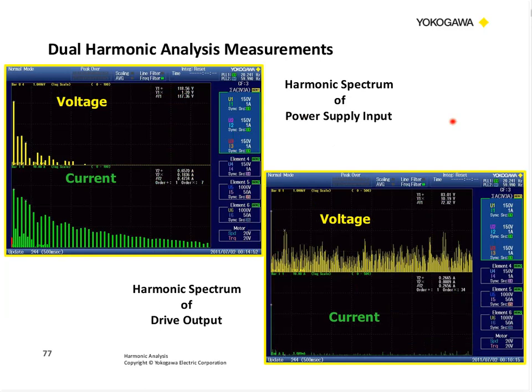So in our dual harmonics, this would be the power supply input to the drive, and a lot of harmonic content on the current side, and the voltage drops off pretty quick, not too much. But then when we look at that PWM output, we know we have a tremendous amount of harmonic content on the voltage side. And you'll see some beat frequencies in there. Then the current is pretty much right there in the fundamental. So even though we have a lot of high harmonic content, where's all the power? Power is right here in the fundamental.